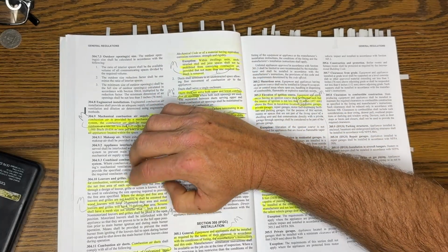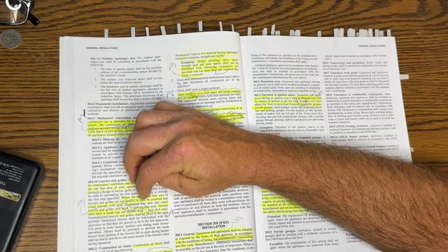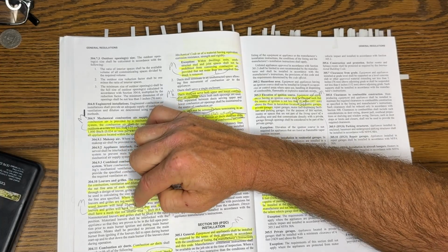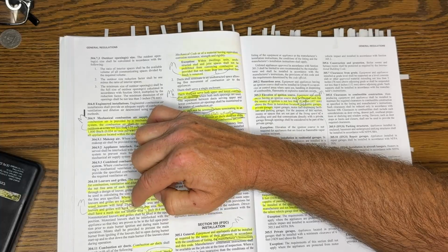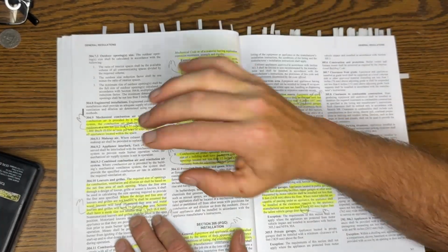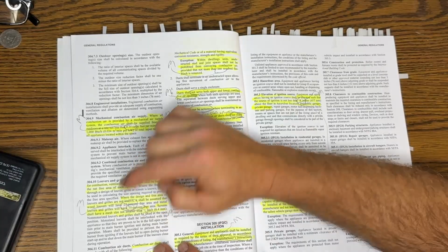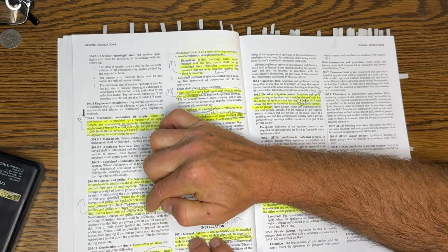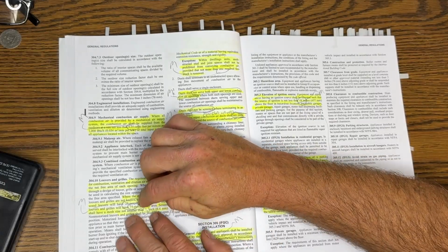Okay, louvers. This does come up. Wood versus metal. It shall be assumed that wood louvers will have a 25% free area and metal louvers shall have a 75% free area. So when you're putting louvers on those openings, you have to derate it based upon these values, okay? Screens shall have a mesh size not smaller than 1/4 inch. So just keep that in mind.